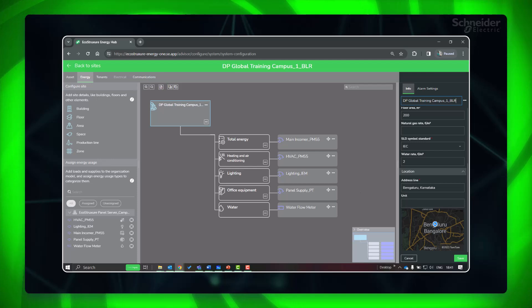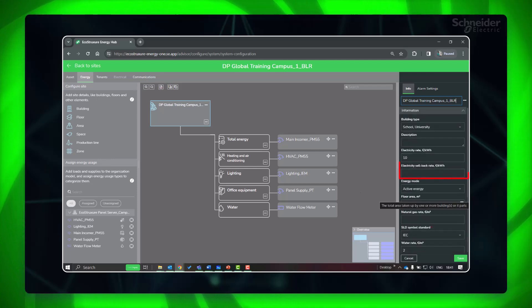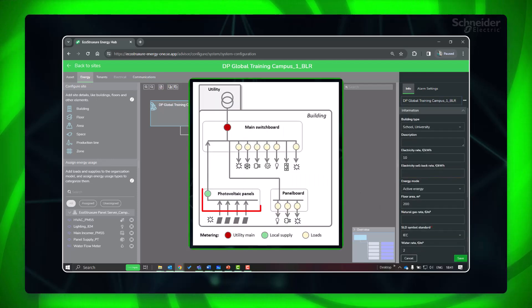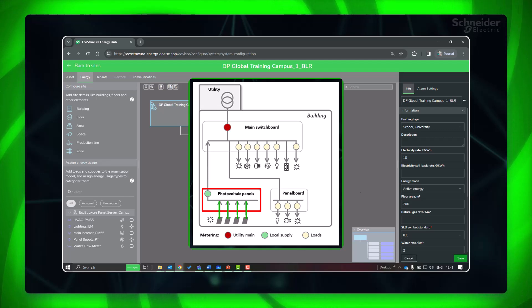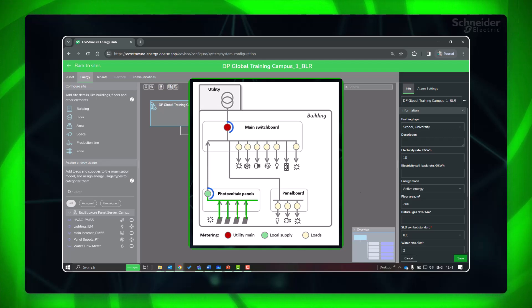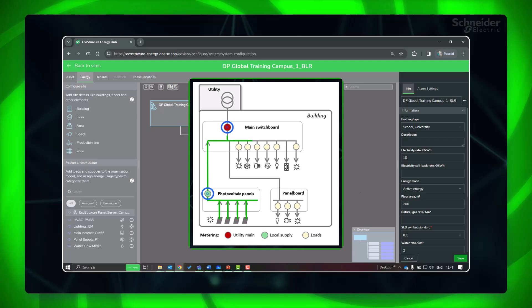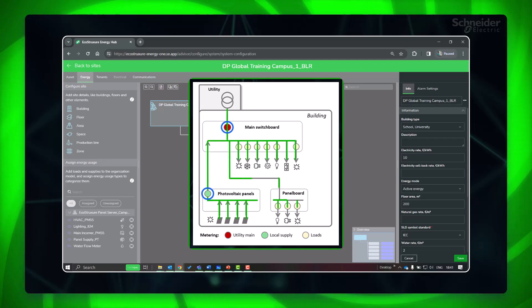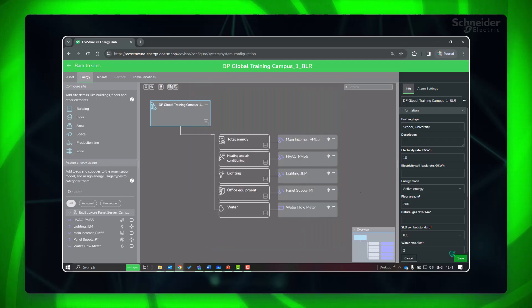Electricity sellback rate needs to be set if there is an on-site generation that is connected to a main incoming feeder at a building or site level. Bi-directional monitoring devices need to be used for incoming utility supply and on-site generation.